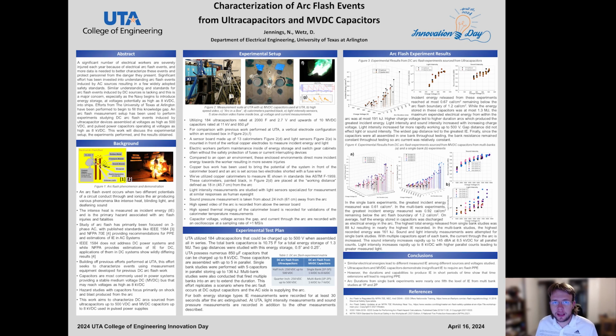The potential across the gap, once the arc is initiated, shorts the capacitors, and so as a result, there's a voltage drop inside the capacitors. If the voltage drop inside the capacitors is large enough to not be able to sustain the arc for long durations, then the arc just quickly extinguishes. But for longer durations, the arc is able to sustain. However, at the same time, the energy inside of the capacitors is being drained.